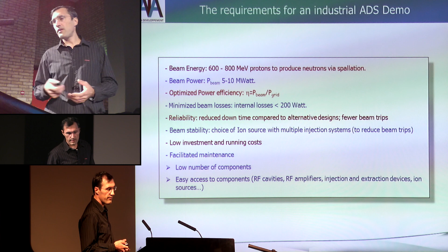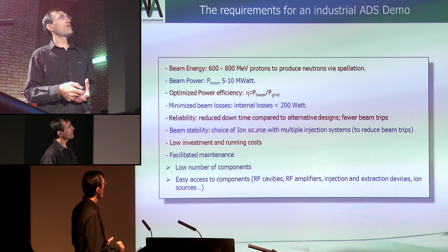We need to have a high reliability with low internal losses. It should be fine to reduce the activation of the machine, of course. The low activation will also facilitate maintenance of this machine. We need to have a high stability. It's why we have developed a new ion source system based on 3 parallel injection lines. Of course, we need to have a low-cost machine with low investment and running cost.